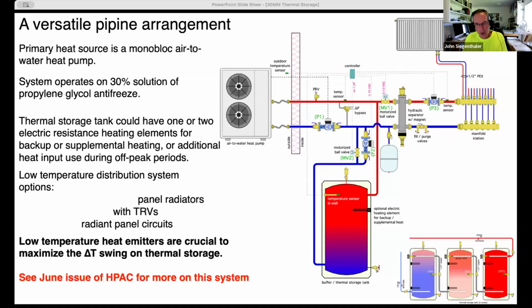So as the flow comes into the tank, the flow is introduced slowly and gently in the right direction to minimize any disruption, any kind of mixing currents inside the tank. And again, the reason for maintaining stratification, there's a thermodynamic advantage in doing that. Essentially, we have greater usability of the energy in the tank when we preserve stratification versus mixing the tank.